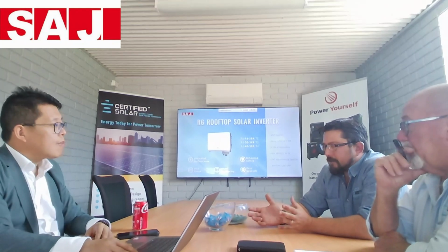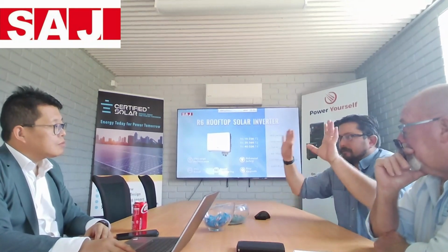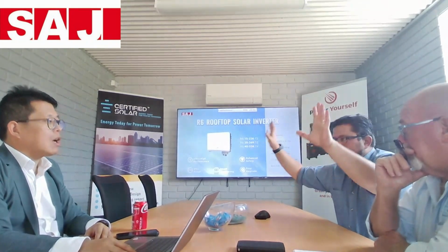Which is huge. And to do that previously, regardless of manufacturer, you used to have to install essentially 3 ten kilowatt three-phase inverters with their own battery systems, paralleled - a real big install. Whereas now we're looking at just the one battery bank, less hardware, so the install becomes more cost effective as well, and you've just got the one product, which is brilliant.